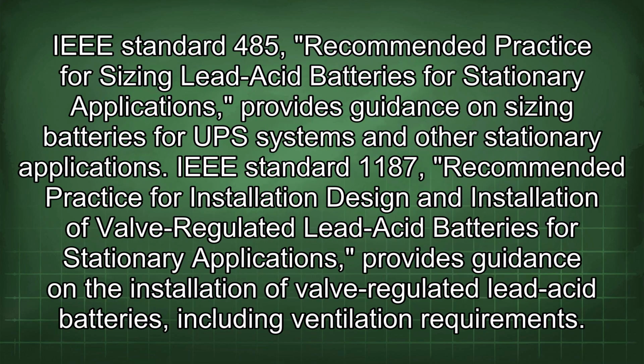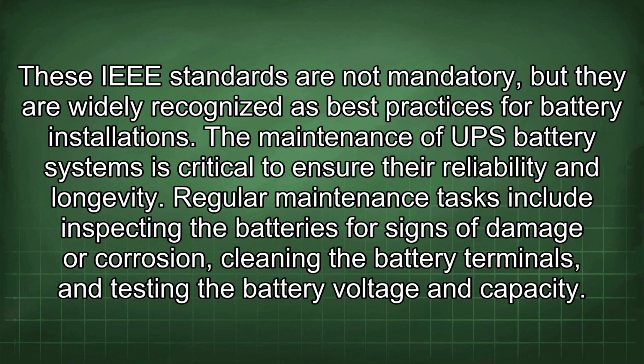and safety. IEEE Standard 485, Recommended Practice for Sizing Lead-Acid Batteries for Stationary Applications, provides guidance on sizing batteries for UPS systems and other stationary applications. IEEE Standard 1187, Recommended Practice for Installation Design and Installation of Valve-Regulated Lead-Acid Batteries for Stationary Applications, provides guidance on the installation of valve-regulated lead-acid batteries, including ventilation requirements. These IEEE standards are not mandatory, but they are widely recognized as best practices for battery installations.